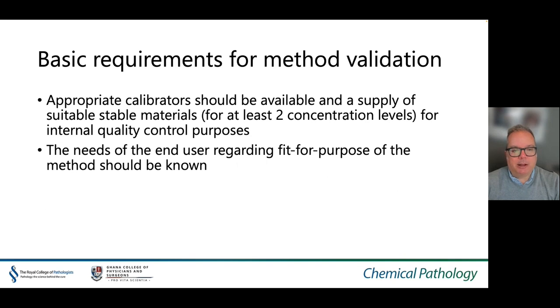Appropriate calibrators should be available, and a supply of suitable material at at least two concentrations for internal quality control purposes must be available. The needs of the end user regarding fitness for purpose of the method should also be known.